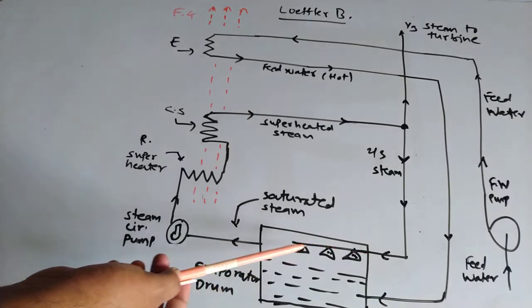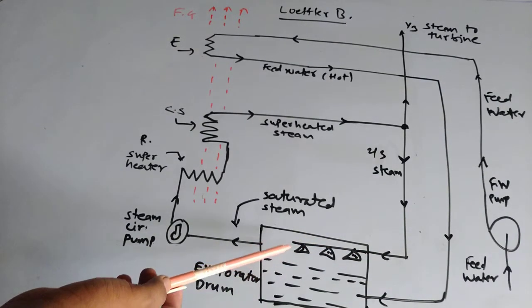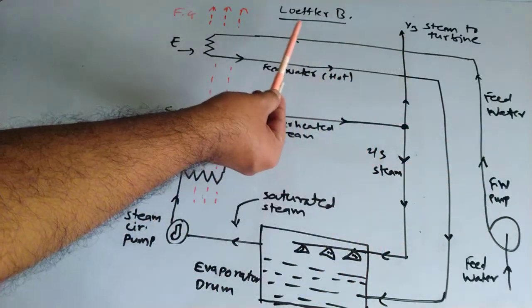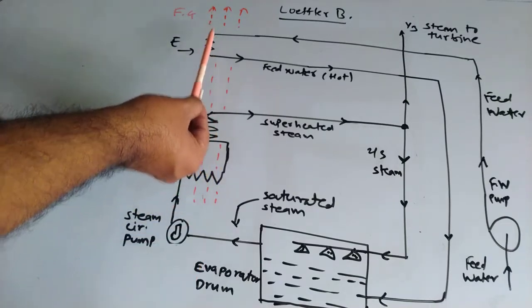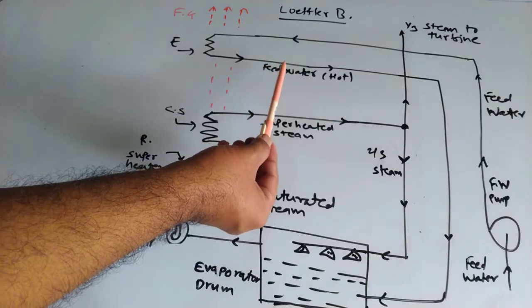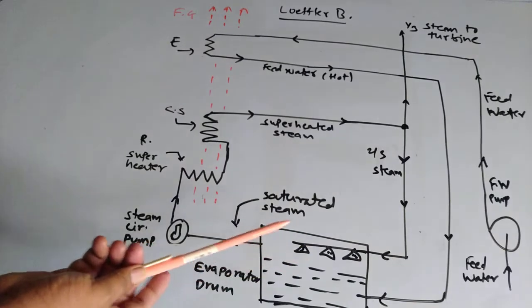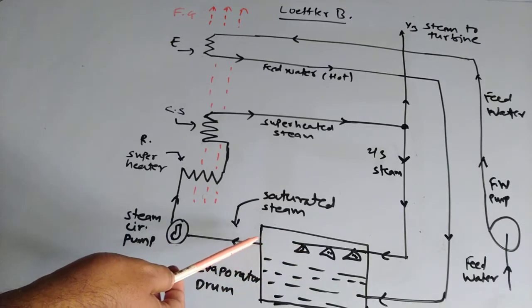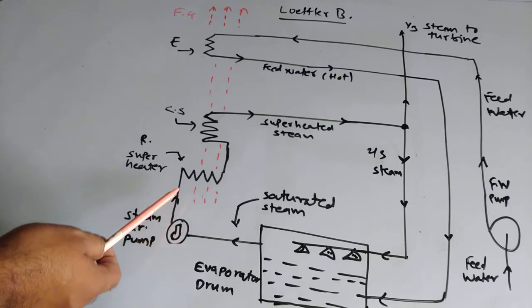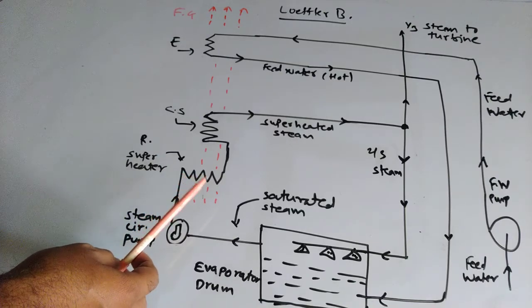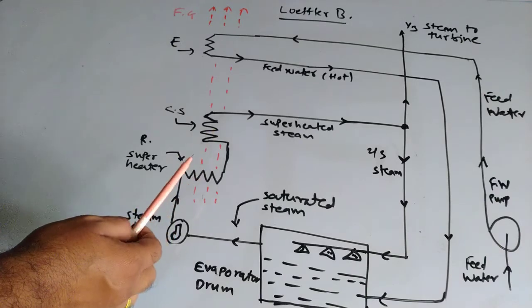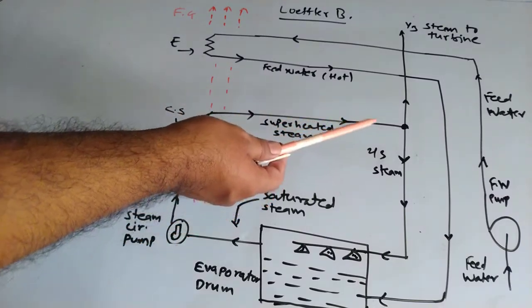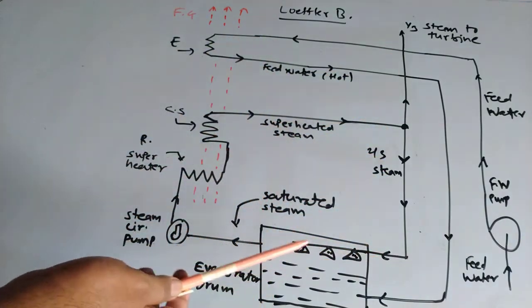Through nozzles, the steam enters the evaporating drum and the cycle is repeated. Feed water comes into the economizer via the feed pump, is preheated by flue gases, and is collected into the evaporating drum where it mixes with the steam already present. That saturated steam is circulated by the circulating pump to the radiant superheater, heated by flame radiation, then sent to the convection superheater where it becomes superheated. One third of that superheated steam proceeds to the turbine, and two thirds returns to the evaporating drum.